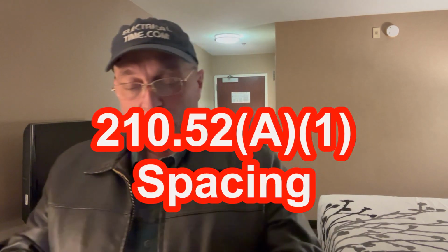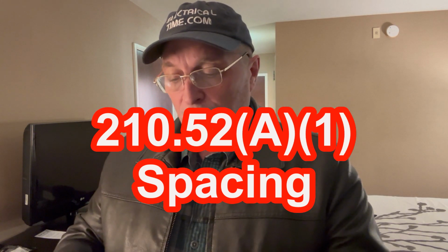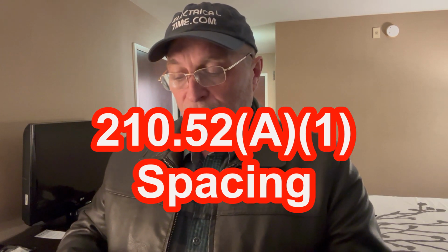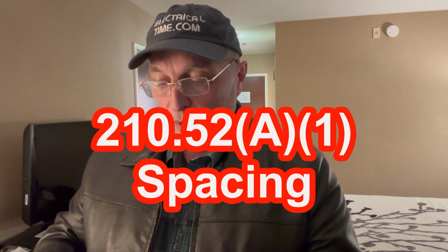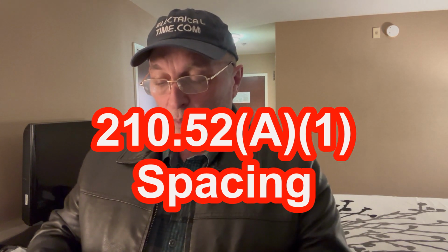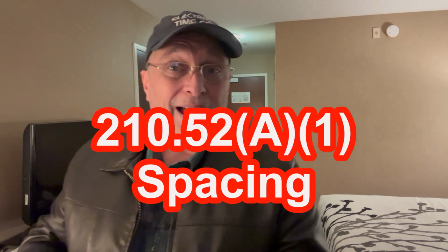All right, so A1 is called spacing. And what it says, receptacles shall be installed such that no point measured horizontally along the floor line of any wall space is more than 6 feet from a receptacle outlet.